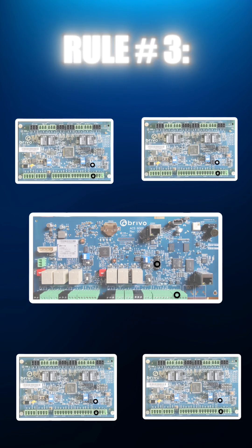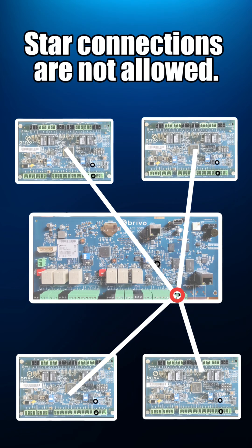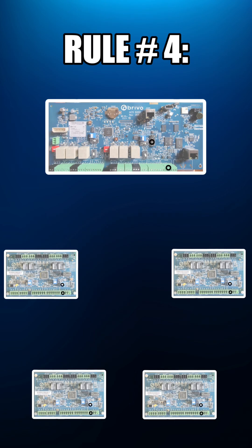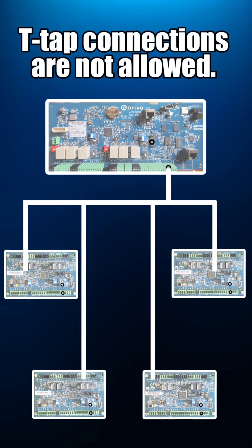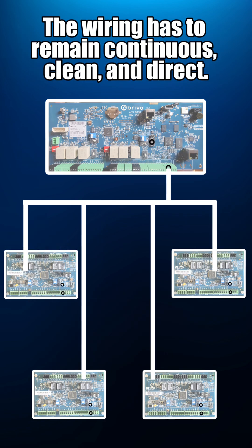Rule 3: Star connections are not allowed. Wiring must follow a straight path from board to board without branching. Rule 4: T-tap connections are not allowed. The wiring has to remain continuous, clean, and direct.